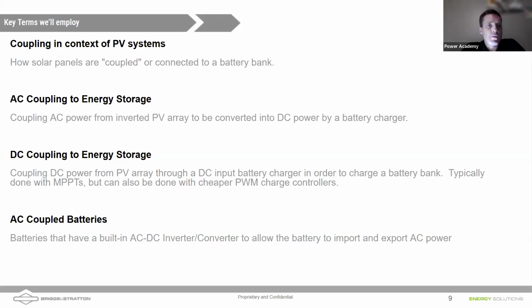DC coupling to energy storage. Coupling DC power from a solar array through a DC input battery charger in order to charge a battery bank is typically what we're going to refer to as DC coupling. So this is coupling without the use of an intermediary inverter like a string inverter or microinverter, right? This is basically taking the DC directly from the solar array, bringing it through some MPPTs, and charging the battery. All DC to DC conversions taking place there, which is much more efficient.